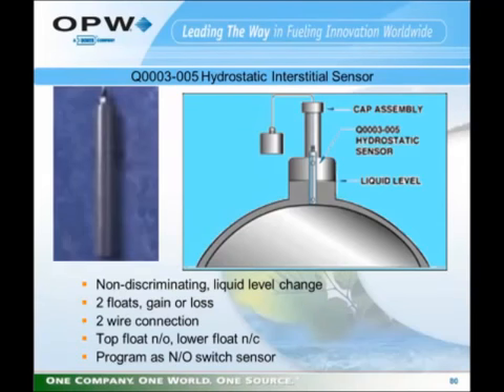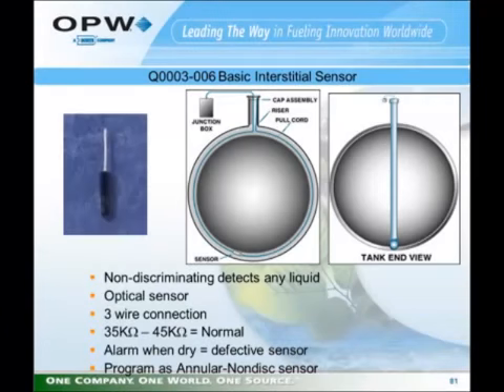The resistance for this sensor, even though it is classed as a normally open sensor, when the sensor is in its normal operating condition, the resistance reading on the two wires would be 40 k ohms. When the sensor is activated in an alarm condition, that changes to 20 k ohms. So it's not truly an open and short like a float switch type sensor would be. So just keep in mind that even though it's programmed as normally open, there is a resistance reading associated with this sensor.